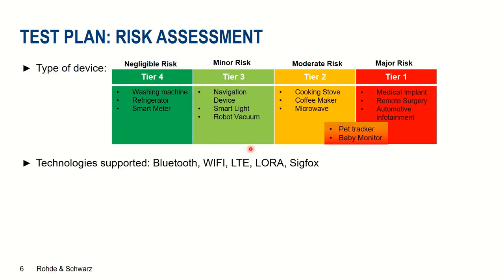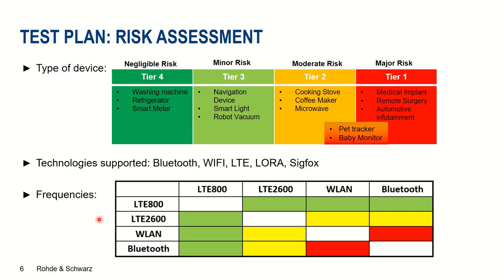The second step in the risk assessment process is to understand what technologies your device under test supports and categorize them in terms of frequency and bands. Then we need to perform a risk assessment matrix analysis. For example, if WLAN operating at 2.4 GHz is my wanted standard, is LTE 800 MHz an interference source? Most likely not — so it's marked green and we can ignore it.